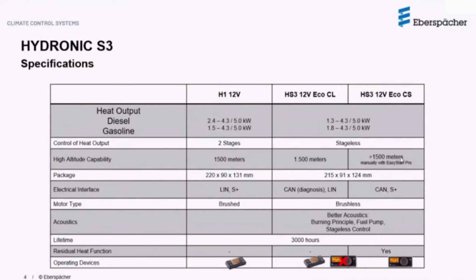In the third generation heater, between the CL and CS versions, only the CS version can be operated in excess of 1,500 meters manually using the Easy Start Pro controller, whereas that's not possible with the CL version. The CL version's maximum elevation is 1,500 meters or 5,000 feet, whereas the CS version with Easy Start Pro can operate up to almost twice as much, about 10,000 feet. From the dimensions and footprint, they are very comparable, pretty much almost the same size.